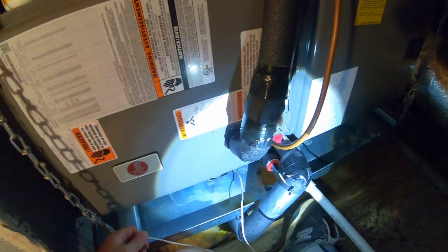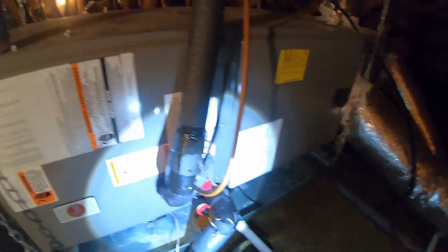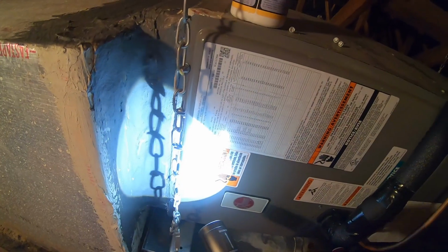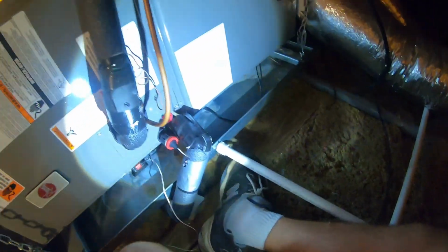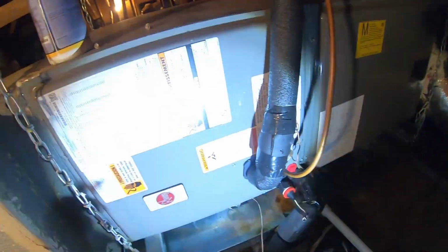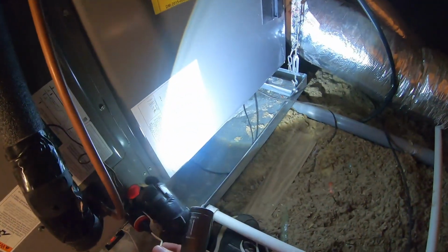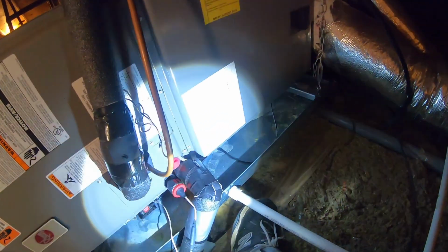And a little trick, you can see how big a unit is designed to run by just looking at the model number. So before you heard me read off that 36 number right there, the RH1T36. The 36 is the BTU rating in thousands, so it's 36,000 BTUs. There's 12,000 BTUs to a ton, so that's a 3-ton blower. All right, so we got that.